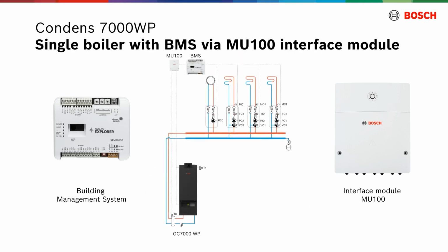The building management system takes over control of the heating system and sends the signal to start the Bosch EMS boiler. Depending on the specific installation, interface module MU100 adjusts the flow temperature or the output of the heat source via an external control signal 0 to 10 volts. The module also signals run and error information in the heat source back to BMS.